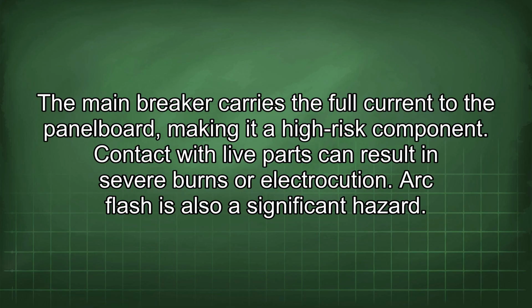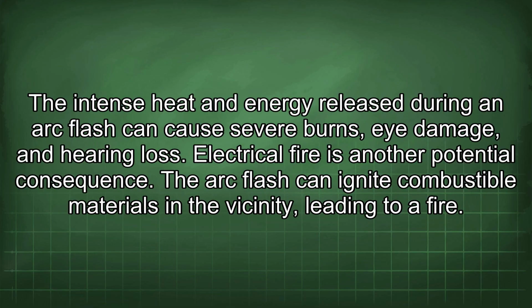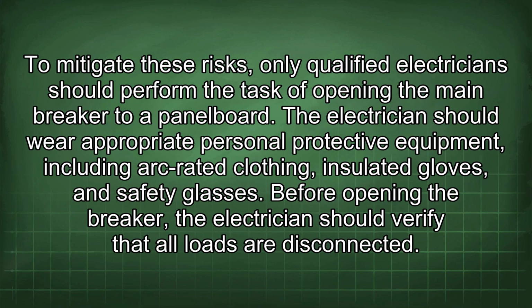Arc flash is also a significant hazard. The intense heat and energy released during an arc flash can cause severe burns, eye damage, and hearing loss. Electrical fire is another potential consequence. The arc flash can ignite combustible materials in the vicinity, leading to a fire. To mitigate these risks, only qualified electricians should perform the task of opening the main breaker to a panel board. The electrician should wear appropriate personal protective equipment, including arc-rated clothing, insulated gloves, and safety glasses.